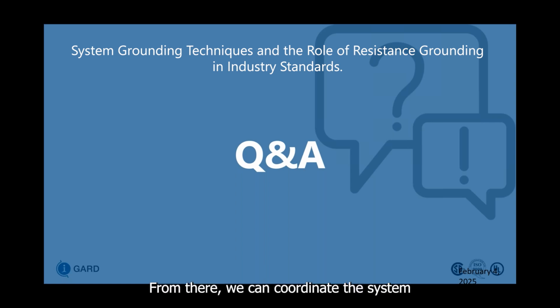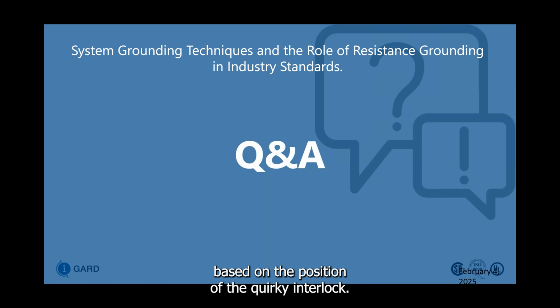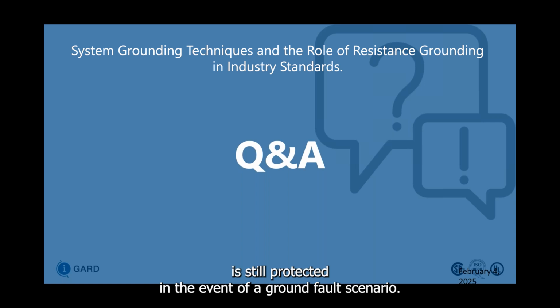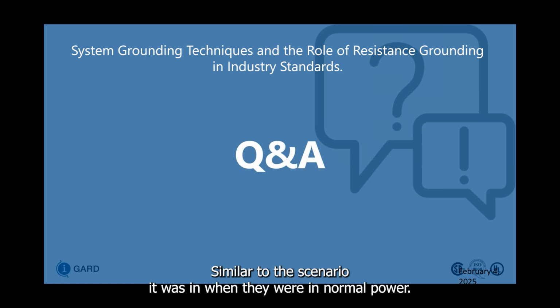From there, we can coordinate the system based on the position of the Kirk key interlock and make sure that the system is still protected in the event of a ground fault scenario, similar to the scenario it was in when they were in normal power.